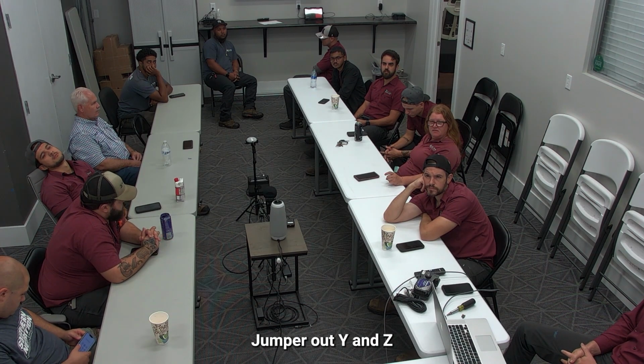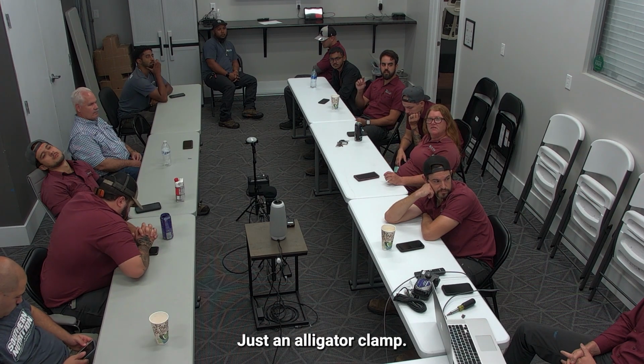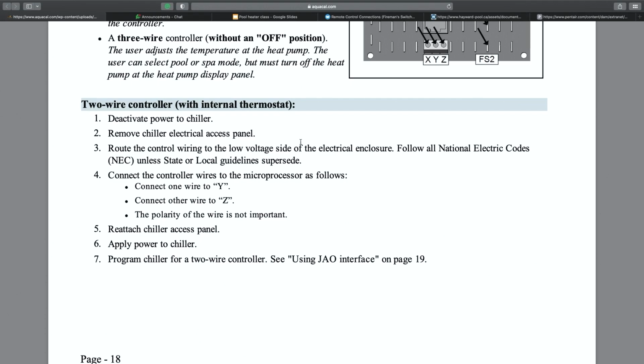Jumper out Y and Z. Yeah, just an alligator clamp. Yep, so you can at a minimum test your heater, right? You get an alligator clamp, and you jumper out Y and Z for the two-wire control, and your heater should come on and run, right? And then you can test everything on the heater and find out that it's fine, and you can let your property manager know you have an issue with the control, not actually the heater. Okay?